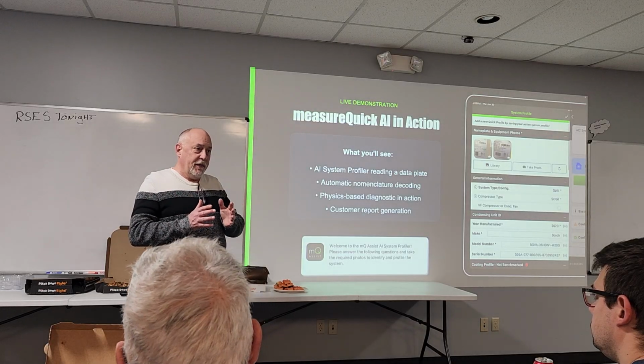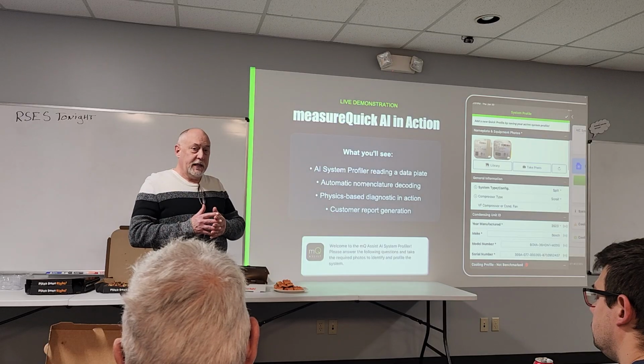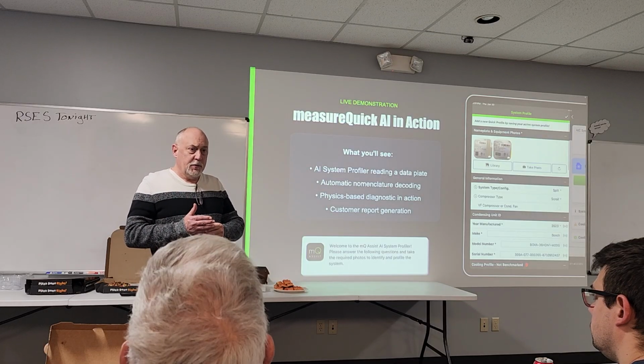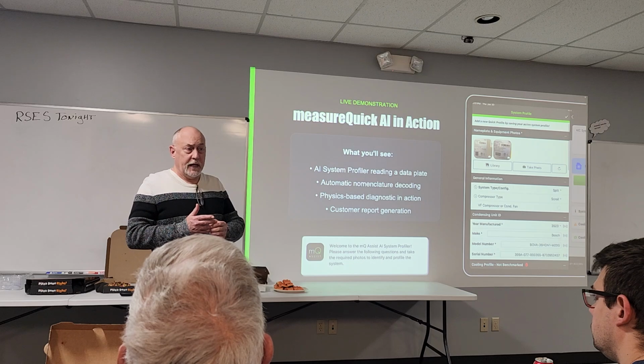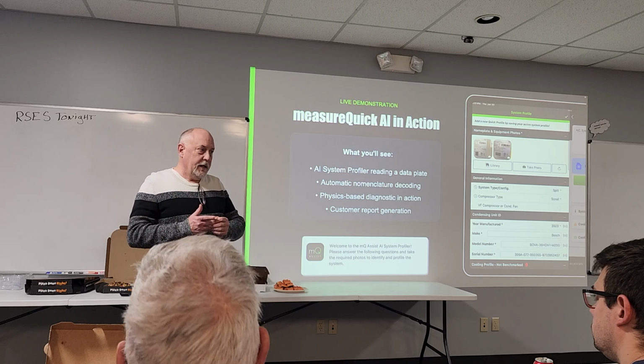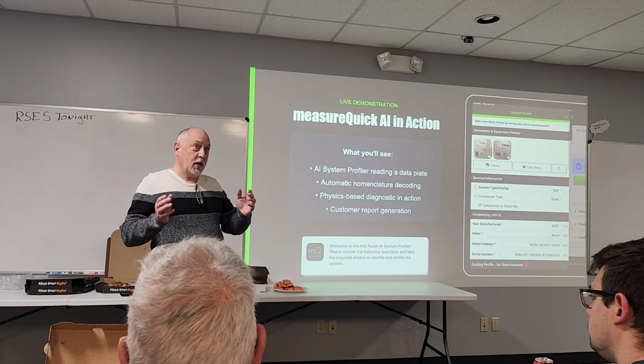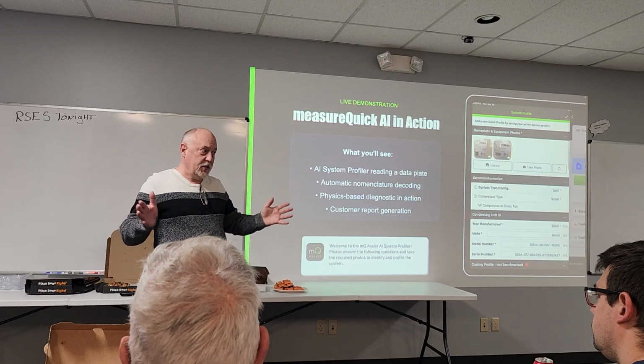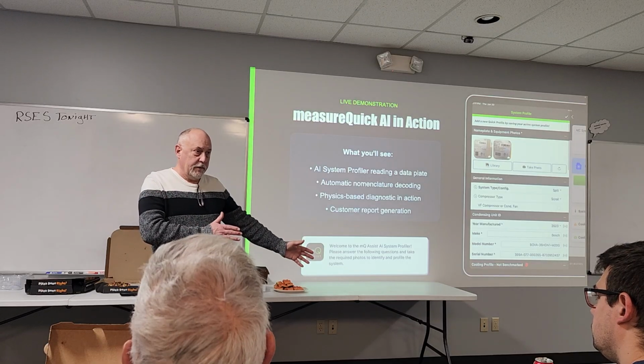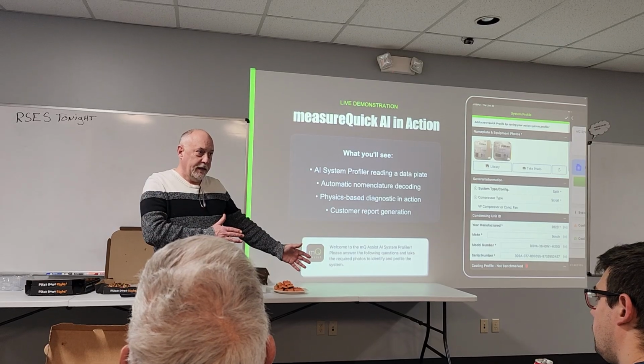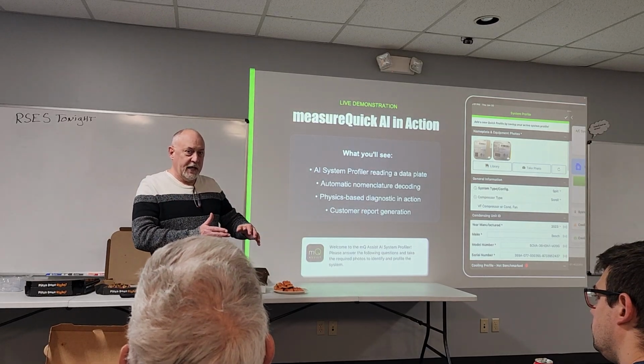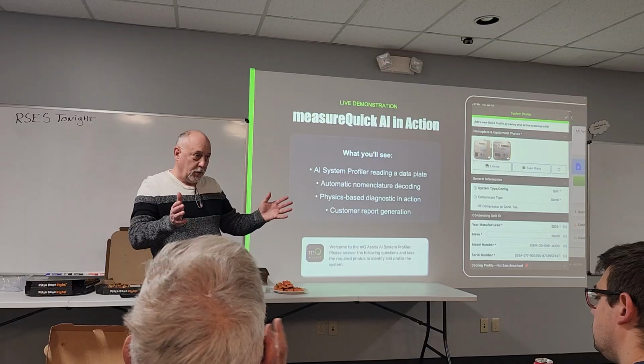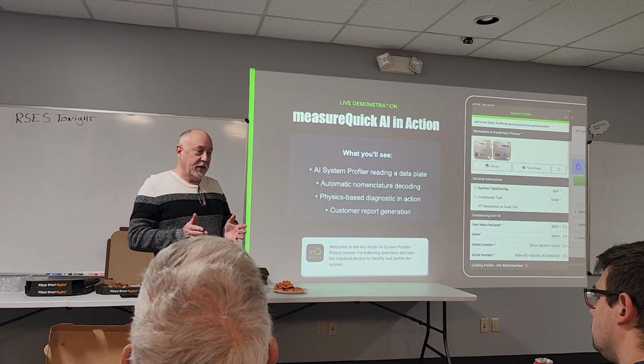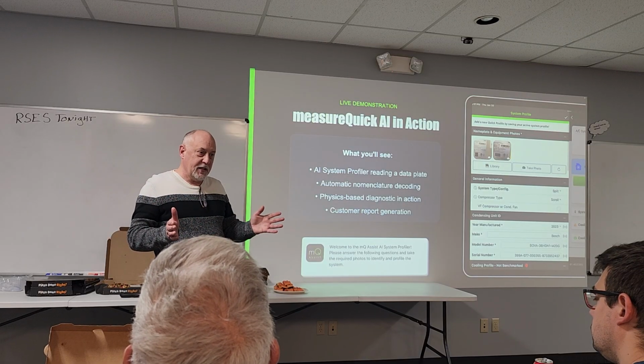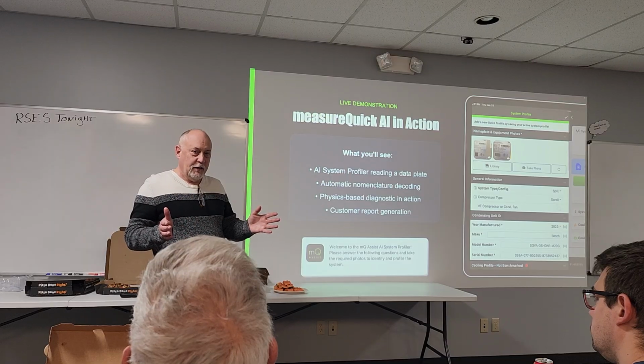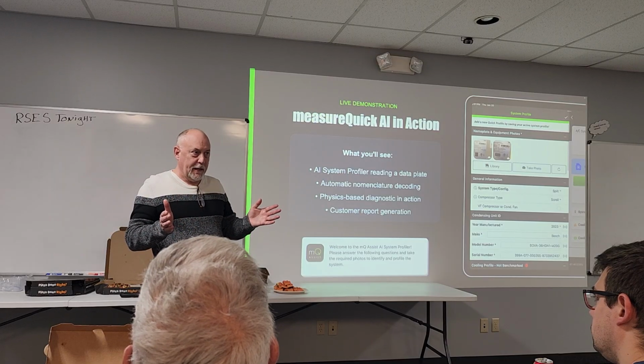We started looking at what things they weren't doing, and their guys were doing things like not deploying static pressure probes, so they were losing ECM motors. They were not doing proper evacuations. Think about when you have a company of that size and you have over 1,000 technicians, you get guys all the way at the bottom that are just starting out, that were landscapers one day, and they got their EPA certification, now they're service technicians and they're just throwing them out to the wolves. You got the white shirt guys that are out there, they can't fix anything, just trying to sell whatever they can sell. You got a handful of technicians that can actually fix things. There's a wide variety in these types of shops out there.